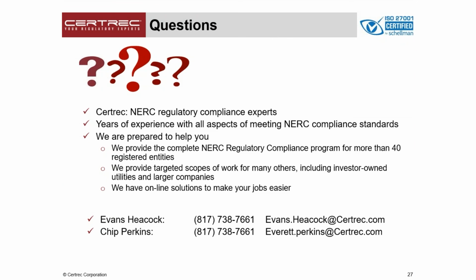I've got a couple of questions here that I wanted to ask. Give us an example of a process that people could use to make sure that they comply with PRC-027? A process would definitely be a procedure that you have in place. It should be part of your compliance program, that you write up how you're going to control and the methodologies for controlling and reviews. Like we talked about earlier, you need to make sure you have a review in there. Your process, which could be a procedure or an analysis, should state how you're following the requirements of PRC-027, and you would want to document that along with the methodology that you're choosing. Make sure you include all your coordination between your transmission, what you're looking at from your transmission and your plant, and the methodology that you're using for option 1, 2, or 3.